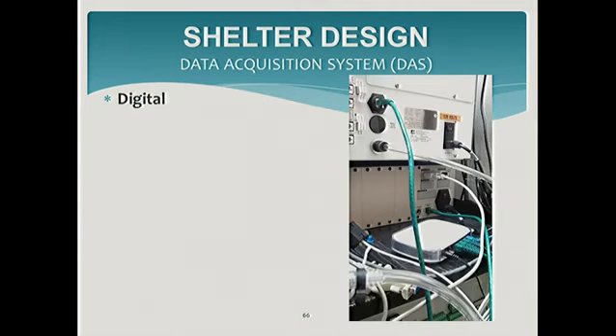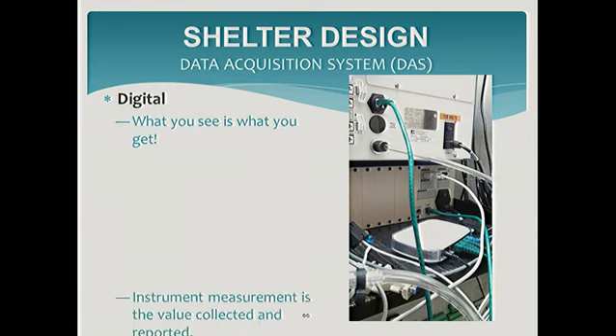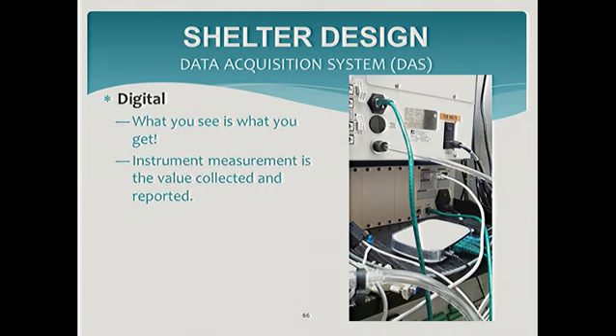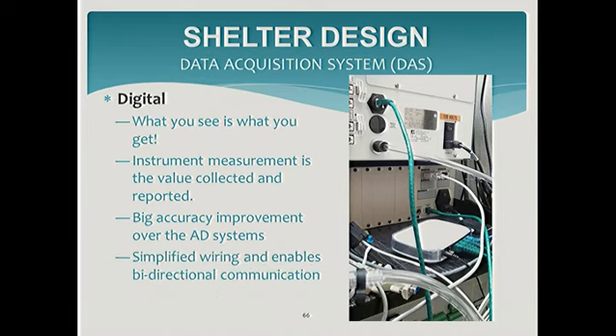So the alternative is, if you're designing a new site, try to go for a digital system. The digital system incorporates direct communication with the instrument for interrogation, capturing internal parameters and metadata for diagnostics. This facilitates tracking of internal settings and parameters, allowing the technician to monitor trends and use the information for more effective preventive maintenance. Basically, what you see in the display is what you get - there are no adjustments, no slopes or intercepts, it's just what it is.